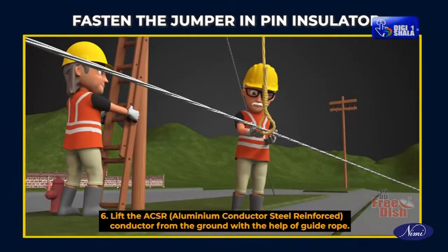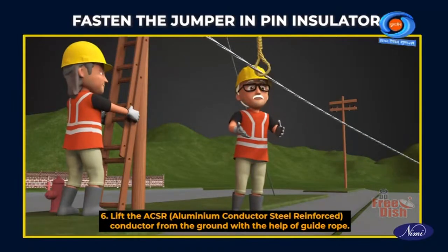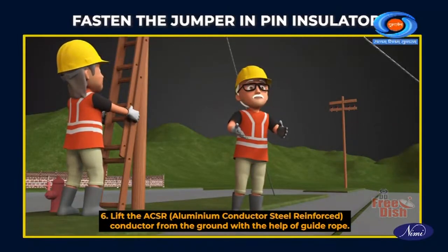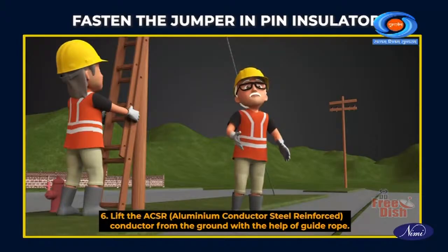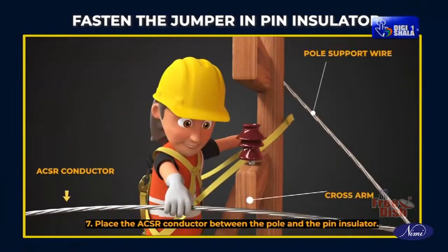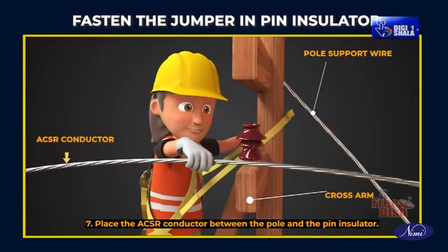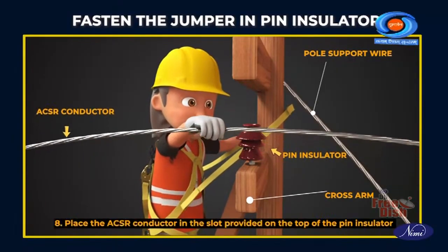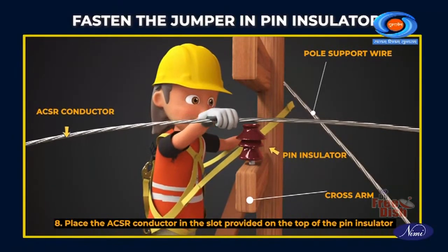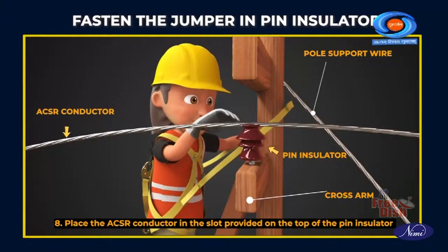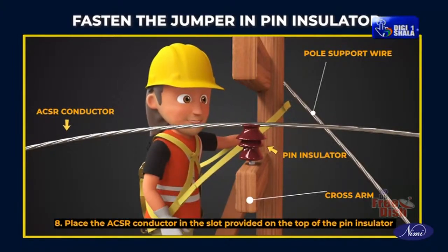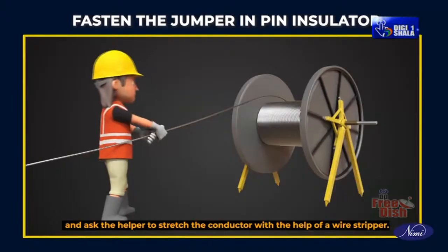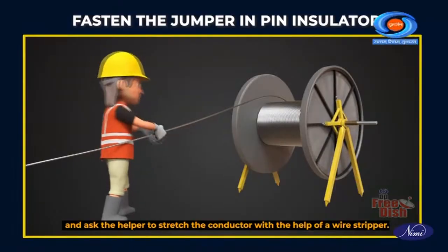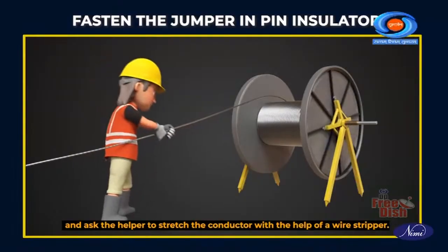Lift the ACSR conductor, that is, aluminium conductor steel reinforced, from the ground with the help of guide rope. Place the ACSR conductor between the pole and the pin insulator. Place the ACSR conductor in the slot provided on the top of the pin insulator and ask the helper to stretch the conductor with the help of a wire stripper.